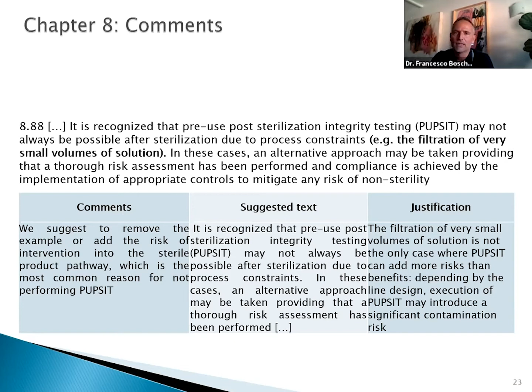So our proposal is: it is recognized that pre-use post-sterilization integrity testing may not always be possible after sterilization due to process constraints. So removing the example. And in this case, everything, of course, will need to be very strongly supported by a risk assessment.